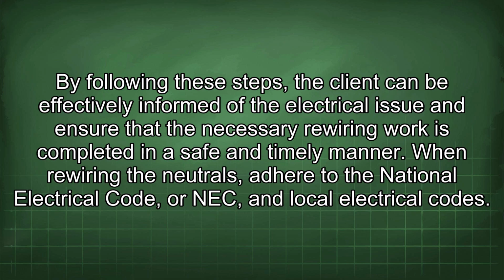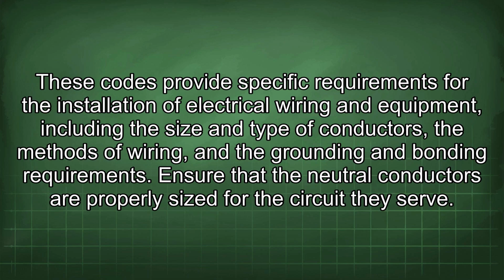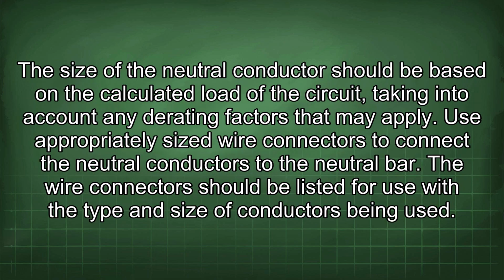When rewiring the neutrals, adhere to the National Electrical Code, or NEC, and local electrical codes. These codes provide specific requirements for the installation of electrical wiring and equipment, including the size and type of conductors, the methods of wiring, and the grounding and bonding requirements. Ensure that the neutral conductors are properly sized for the circuit they serve. The size of the neutral conductor should be based on the calculated load of the circuit, taking into account any derating factors that may apply.